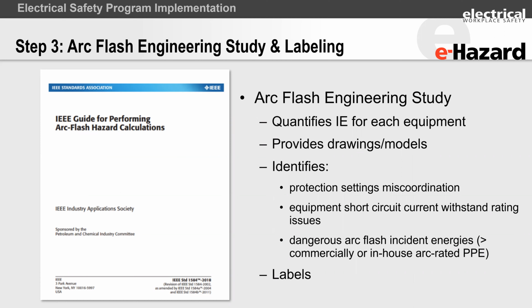So problems like that can be identified as an added benefit when an engineering study is done. But the most important part of the arc flash engineering study is it tells us, for each piece of equipment, what the incident energy is. This means we can determine what is our maximum energy and what is the maximum energy that we wish to protect against. Because folks, remember, not every equipment is going to be aligned to commercially available protection.